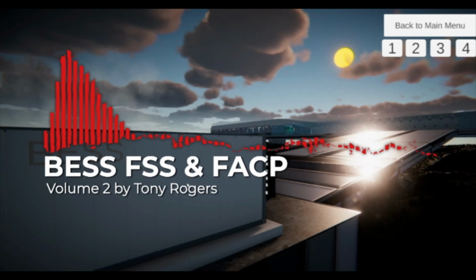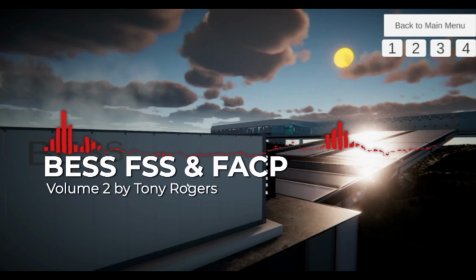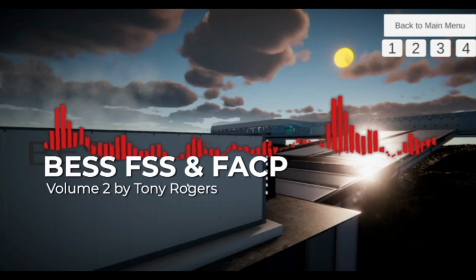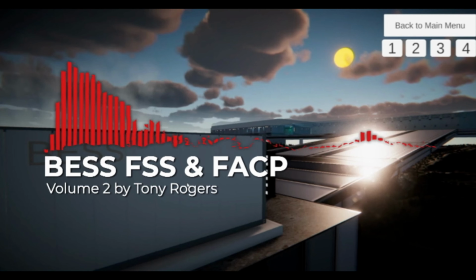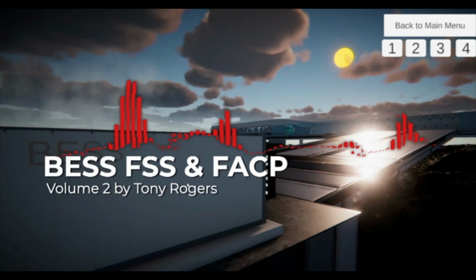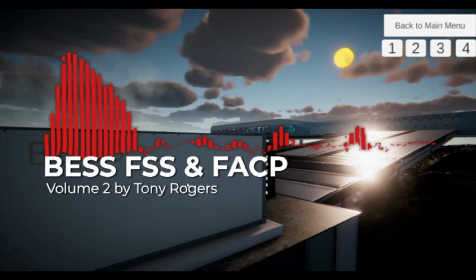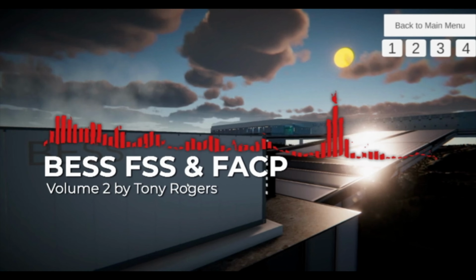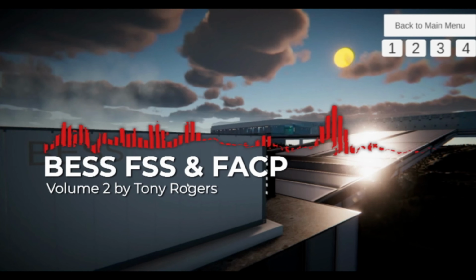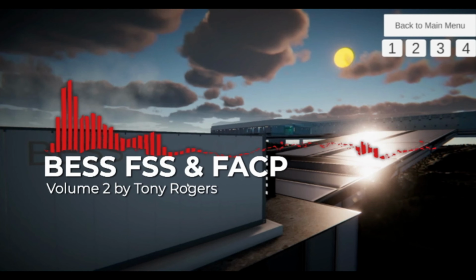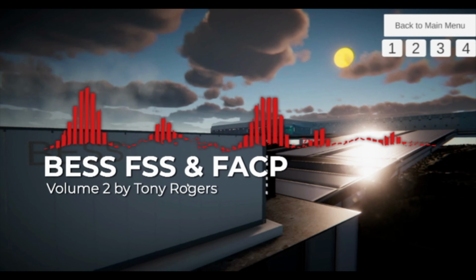Gas levels, ppm, equals sensor output minus zero level divided by the sensitivity factor. This formula is used to calculate the concentration of each gas based on the sensor output, zero level, and sensitivity factor. Hydrogen detection. Hydrogen is a highly flammable gas that poses a significant fire risk. Gas sensors accurately detect hydrogen levels and trigger appropriate response actions to mitigate the danger.